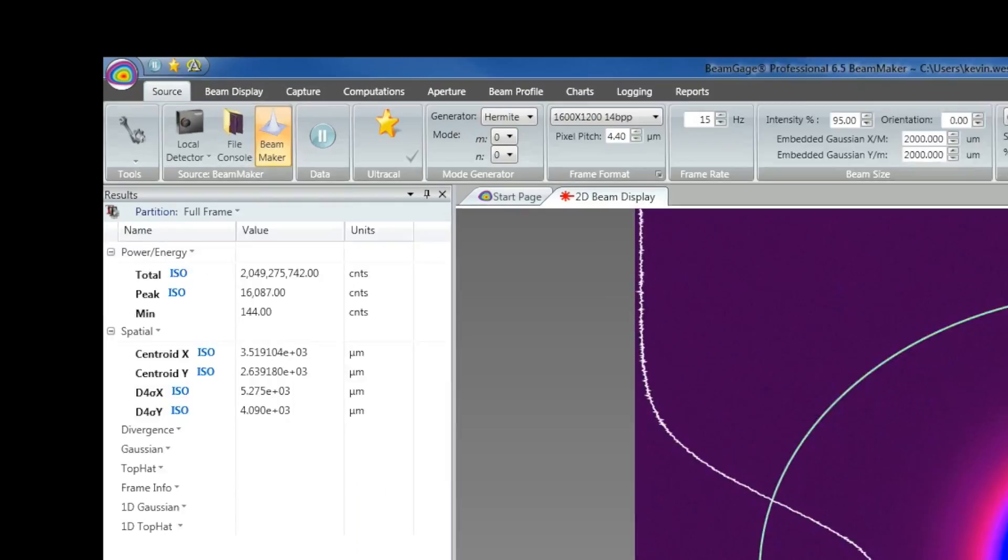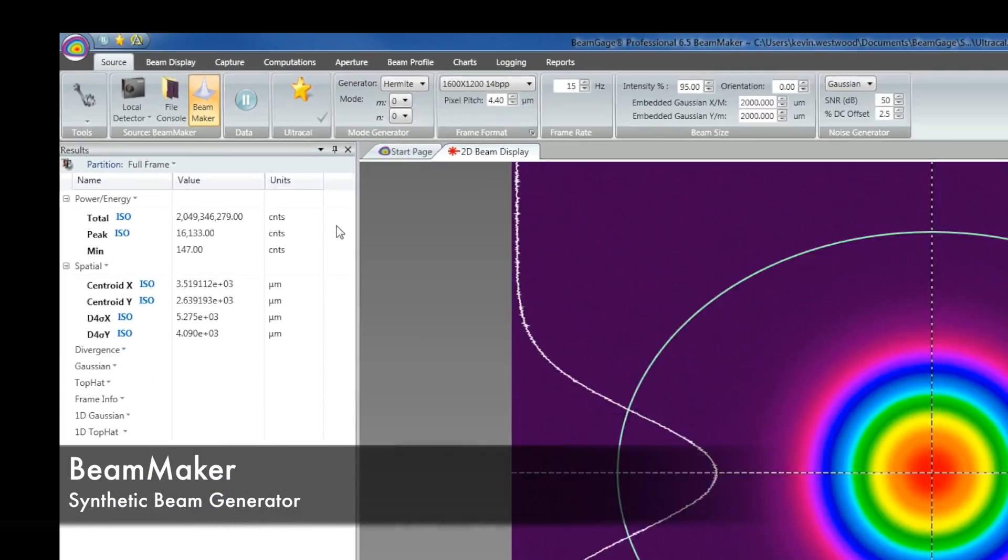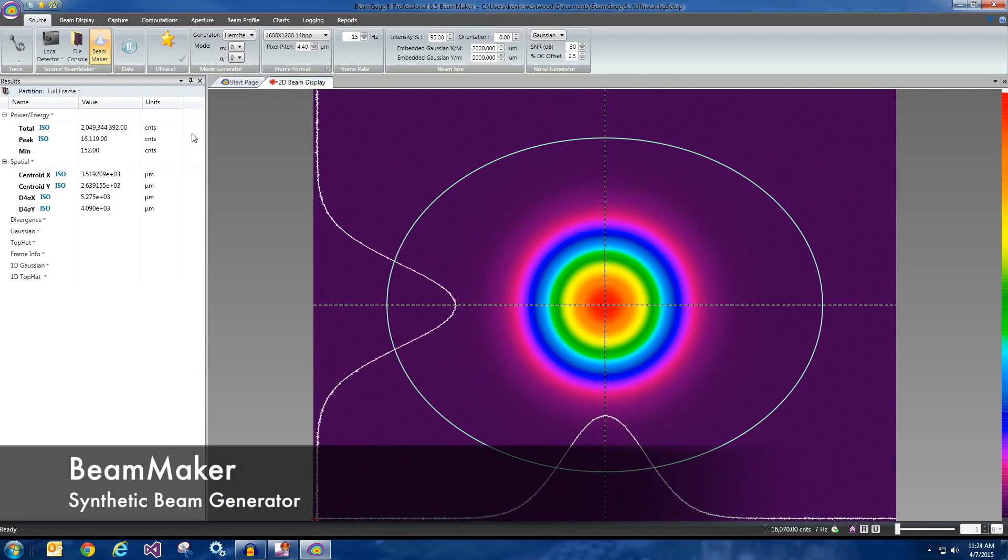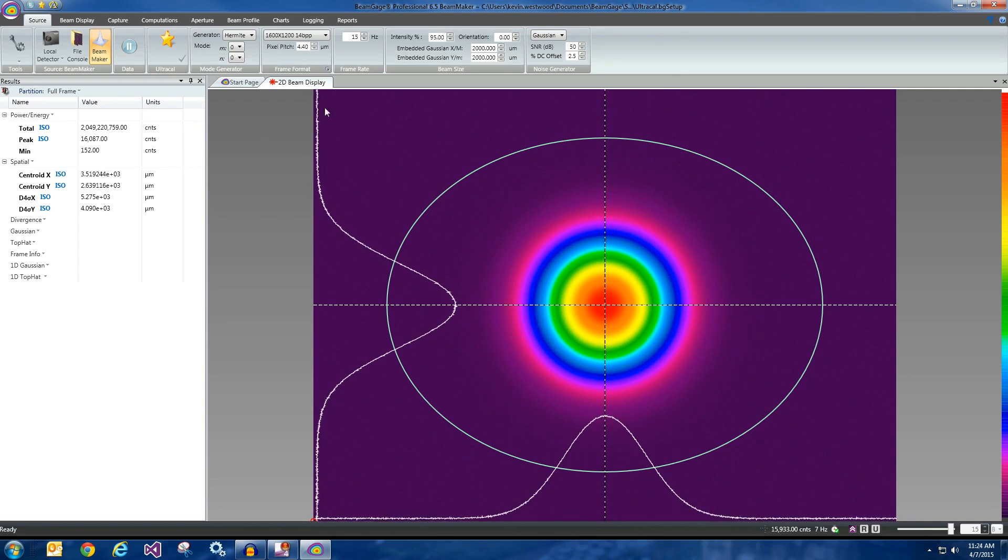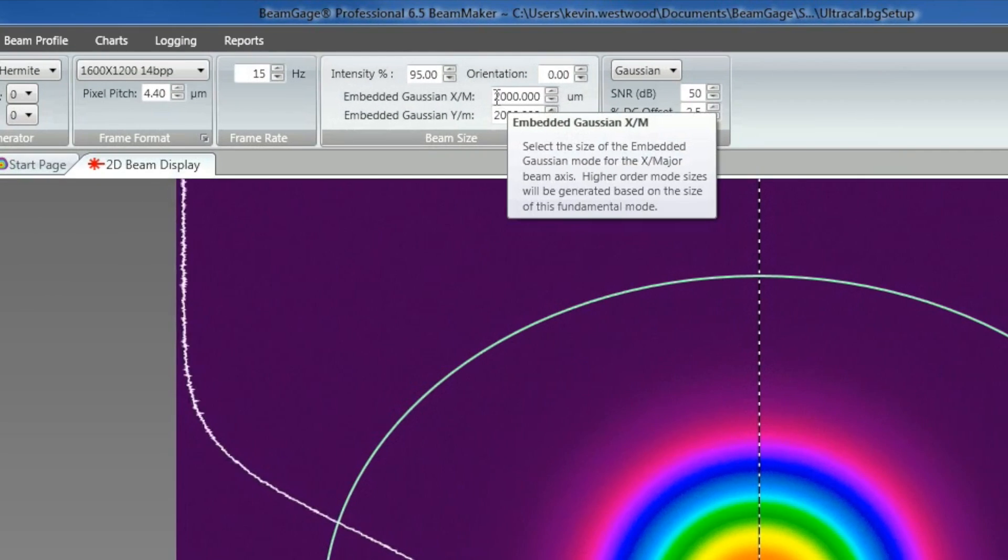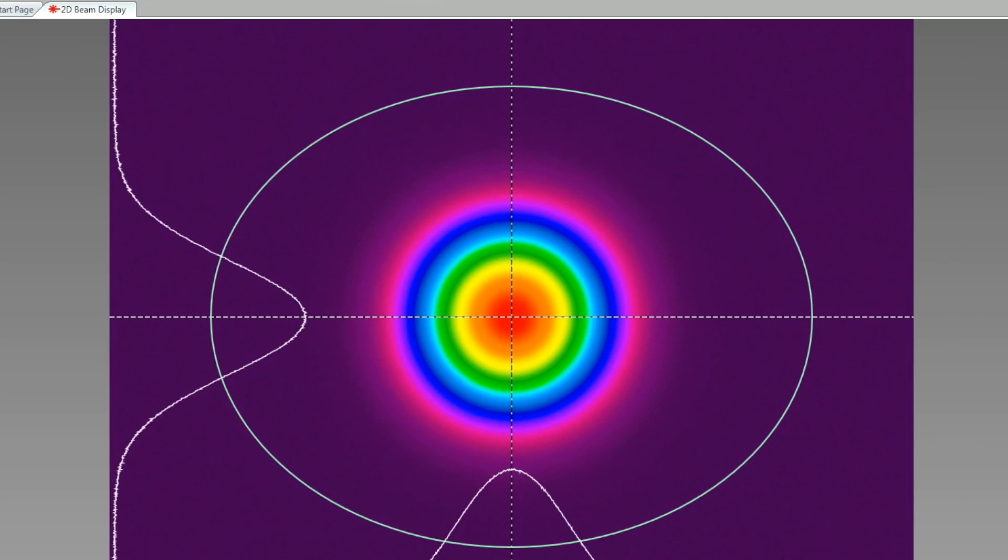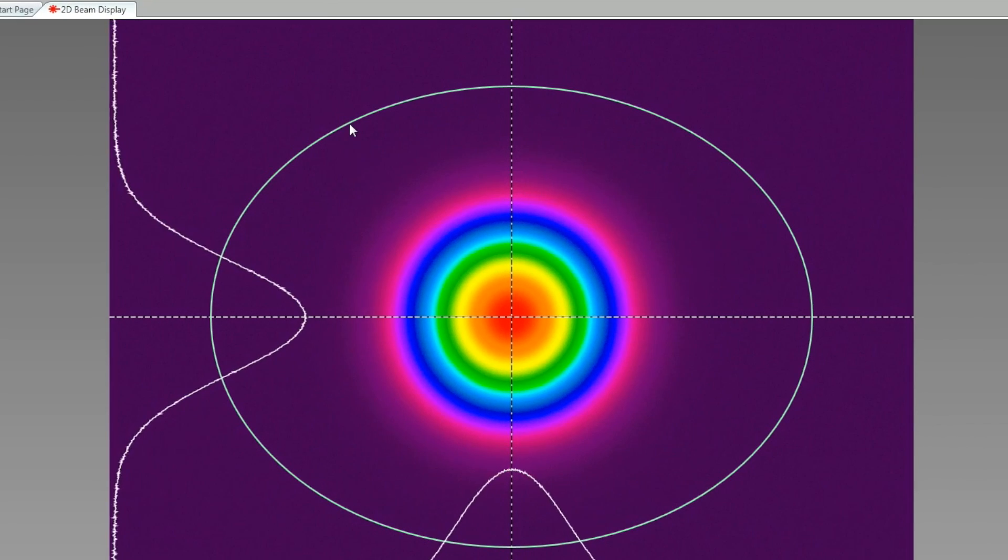BeamGage includes BeamMaker, a synthetic laser beam generator that allows us to use the software as if we were measuring an actual laser. We will configure BeamMaker to generate a 2mm beam. The green aperture shows where BeamGage is calculating the width of our beam.